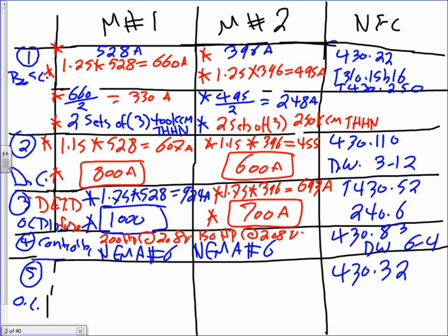Now I want to remind you guys, the first motor has a temperature rise of 40 and no service factor. So what's the multiplier? 1.25, thank you.